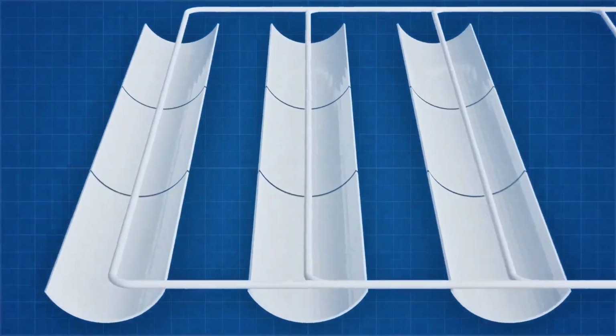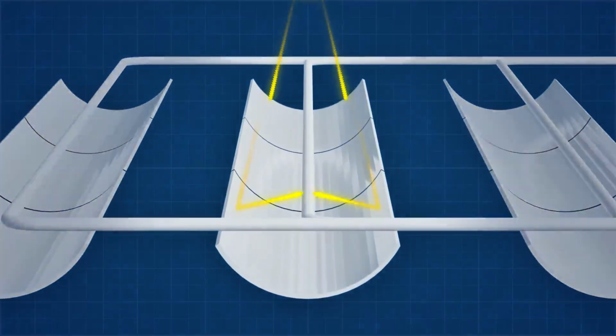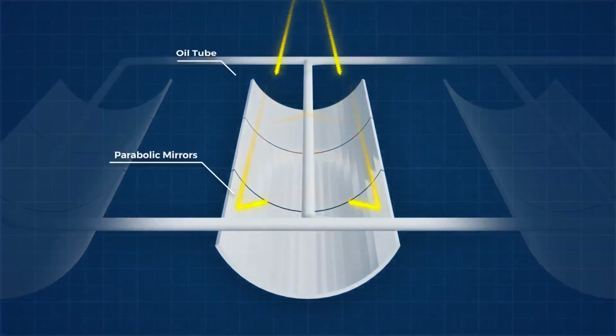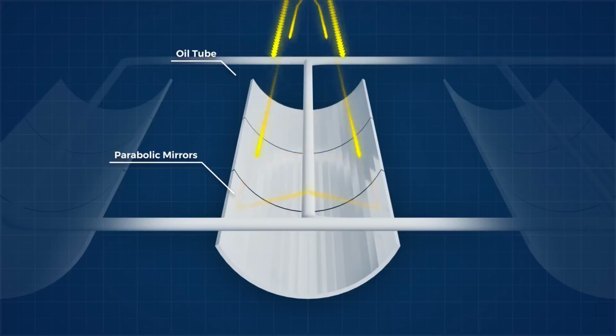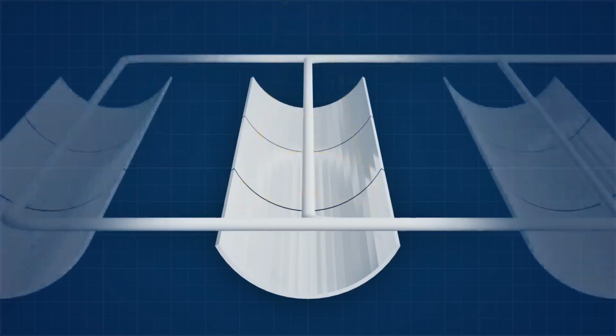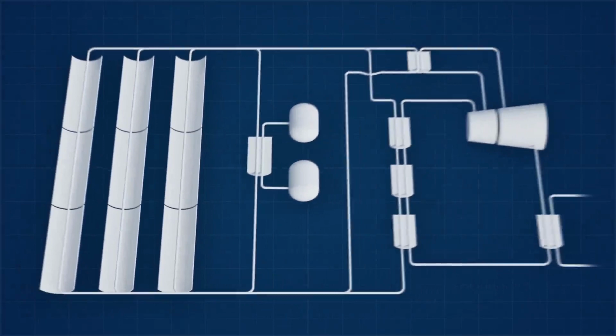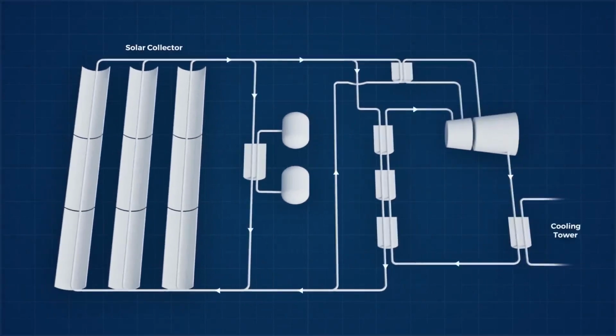Noor 1 and 2 are both trough-based systems that use parabolic mirrors, with the tube located in the mirror's focal point. The tube contains a synthetic oil which collects heat from the 500,000 parabolic mirrors spread out over 308,000 square meters. This oil becomes extremely hot, as high as 400 degrees Celsius, which allows it to boil water in a heat exchanger to drive a steam turbine, which provides electricity for the grid.